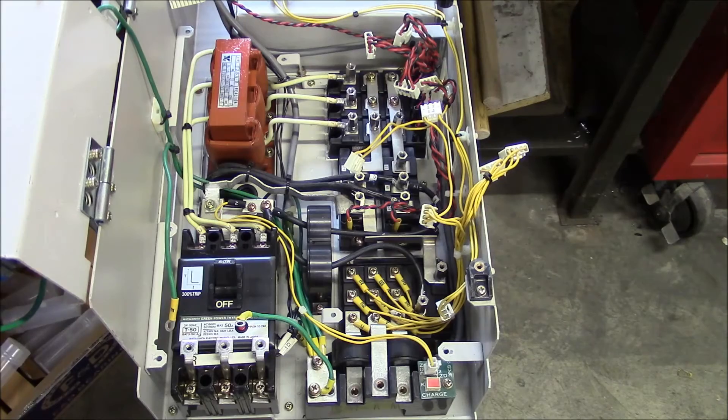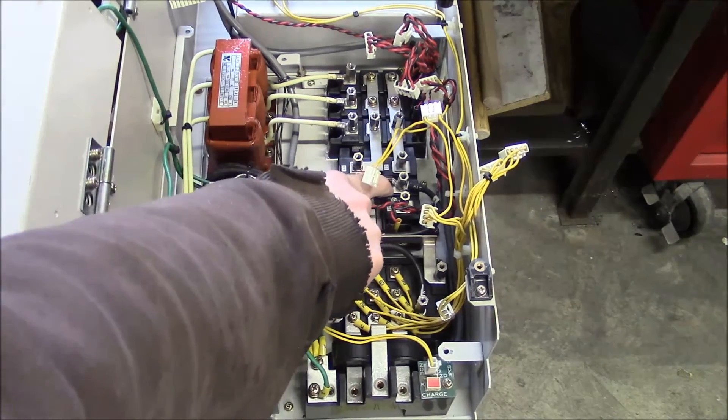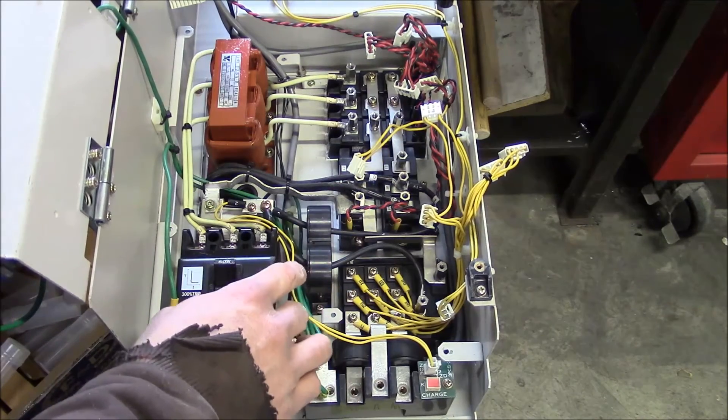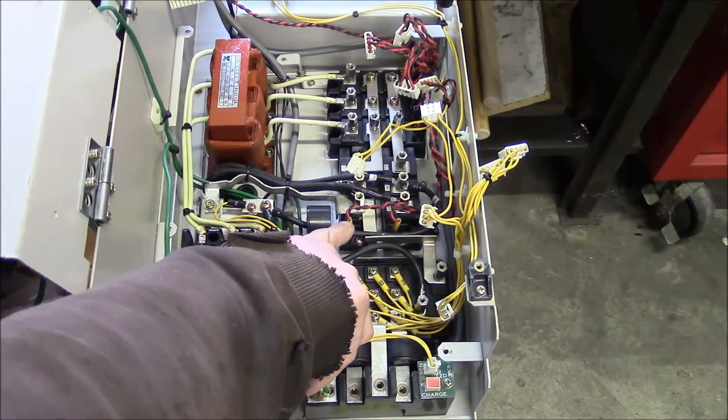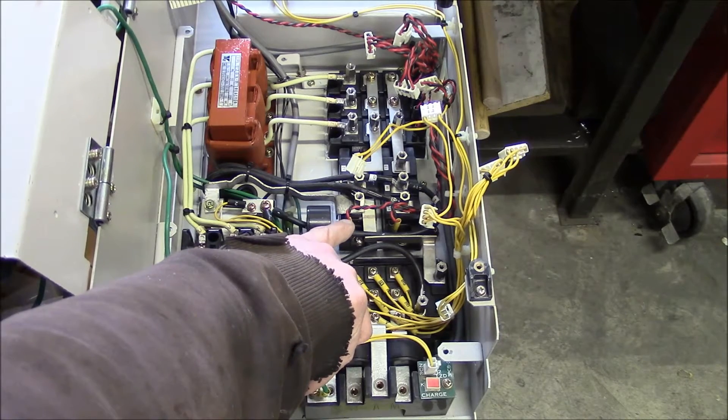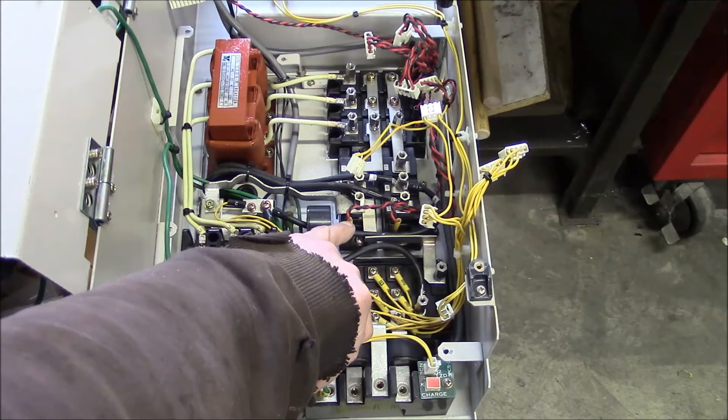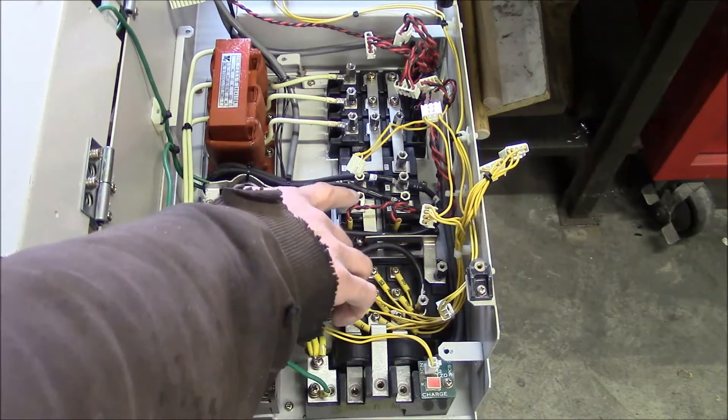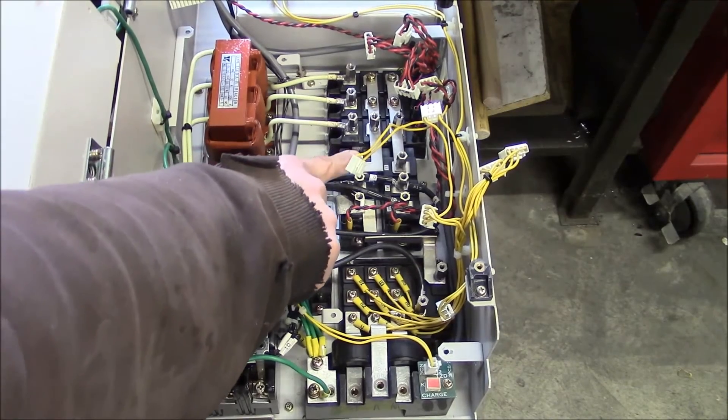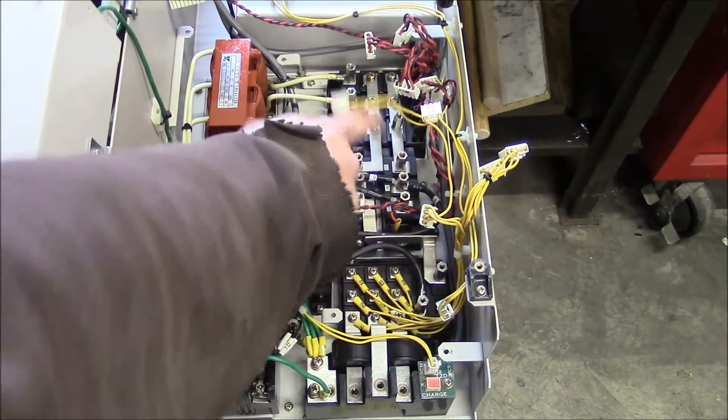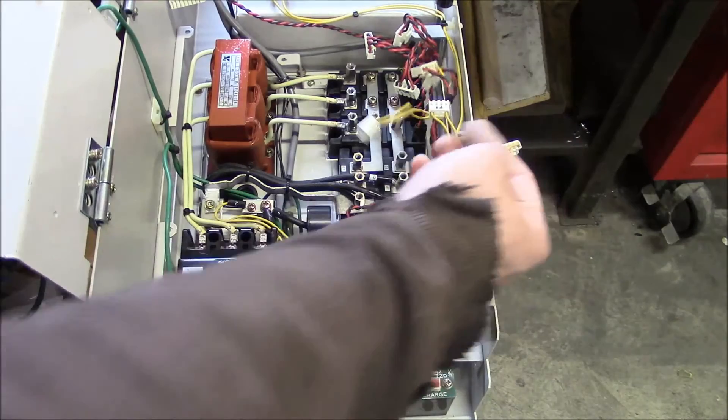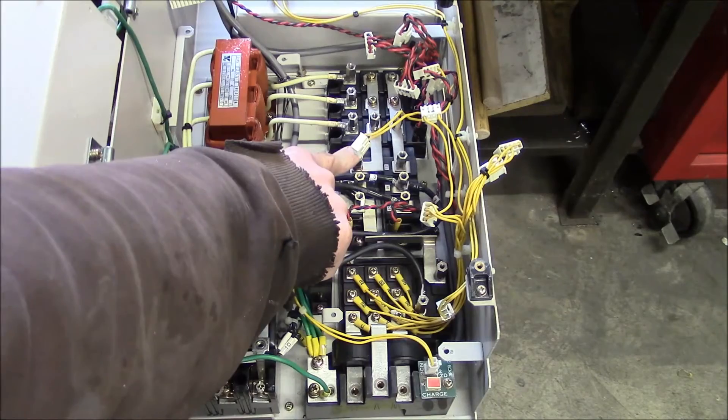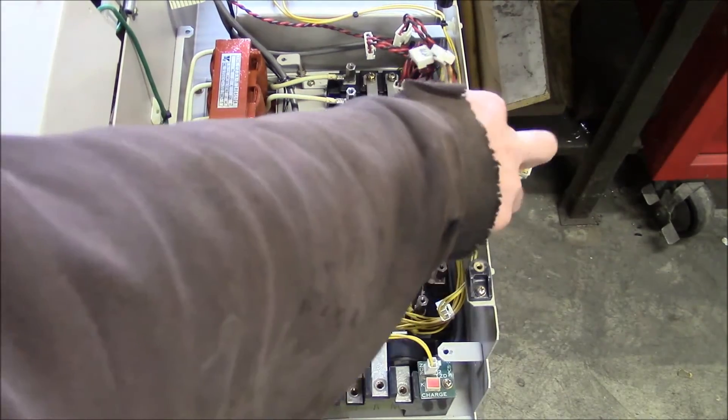Anyway, I took these two IGBT modules out and bench tested them and I applied a 5-volt DC circuit to the emitter and the gate and I was able to test the switching on the IGBTs. And they both switch correctly. So when the voltage is applied to the gate, the current is allowed to flow from the collector to the emitter. So that part of them is working correctly.